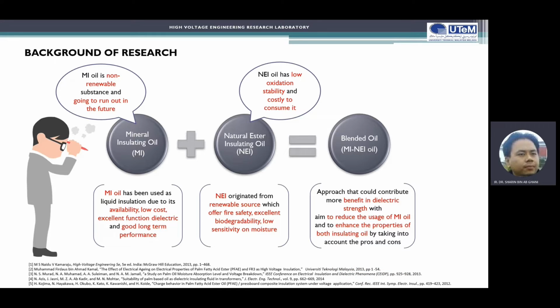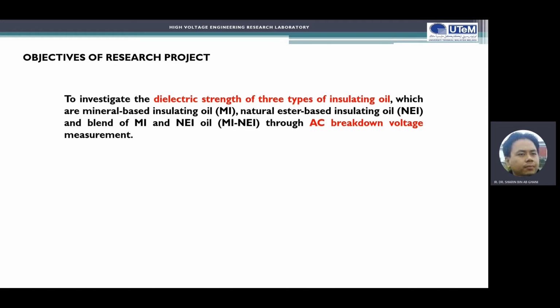Therefore, our project is going to apply blended oil, a combination of mineral and natural ester oil. This approach could benefit dielectric strength, aim to reduce the usage of mineral insulating oil, and at the same time enhance the properties of both oils by taking into account the pros and cons of MI oil and natural ester oil. The objective of this research project is to investigate the dielectric strength of this oil. We produce three types of sample: the mineral insulating oil itself, the natural ester itself, and the blend of the two, measured through AC breakdown voltage measurement.